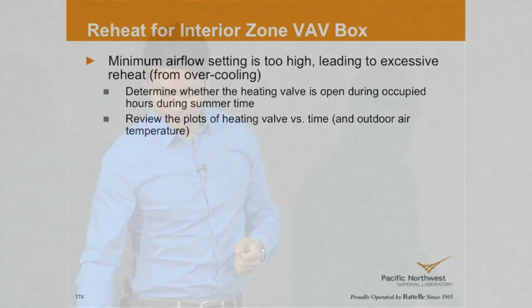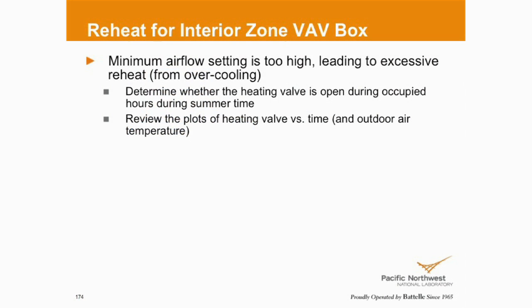A good recommendation Ron just mentioned is that for the perimeter zone, we can have a good setback. Say during unoccupied hours, we can set up like 78 degrees and 68 degrees, and for the interior zone, we can completely shut off. I mean, for all the boxes we can give a wider set point. If the minimum airflow setting is too high, it can lead to excessive reheat. So we want to determine whether the heating valve is open during occupied hours, and review the plots of the heating valve over time.